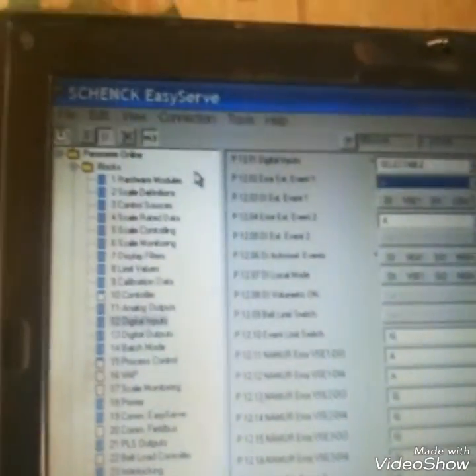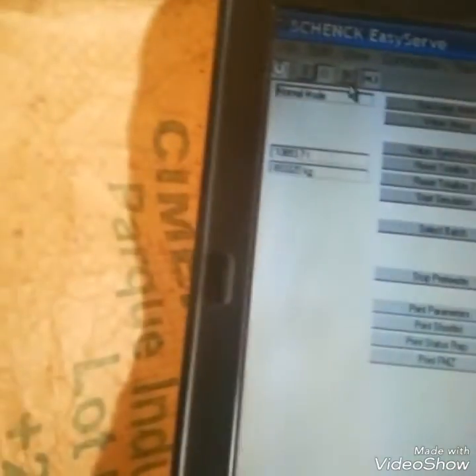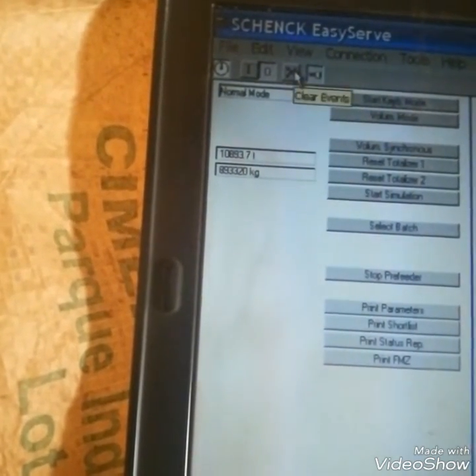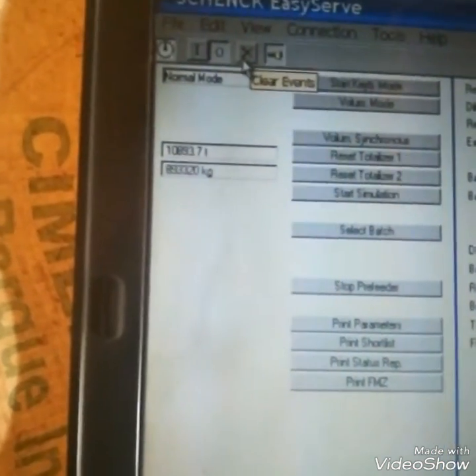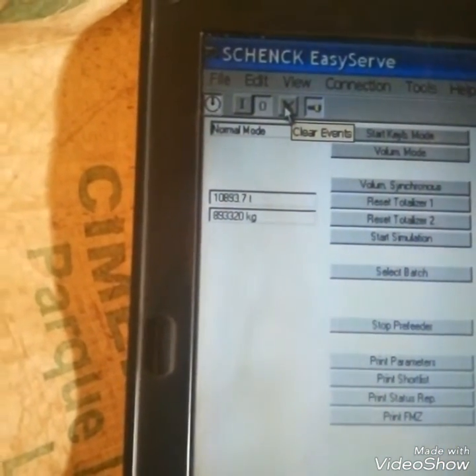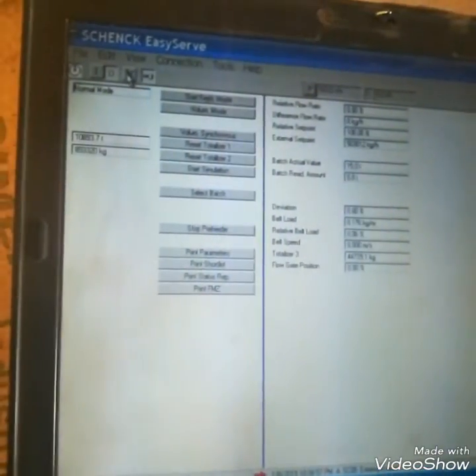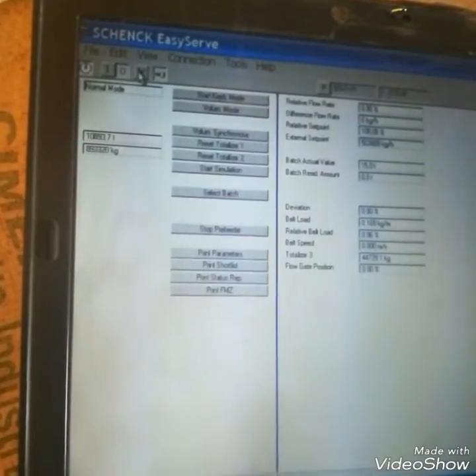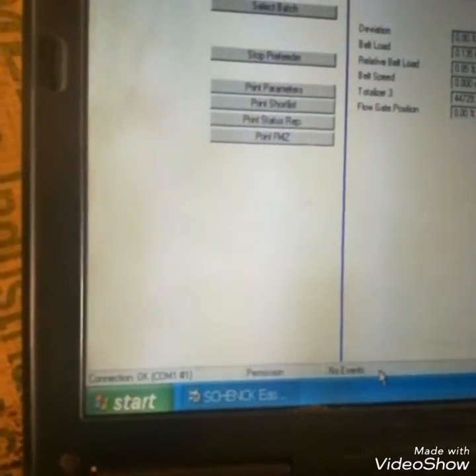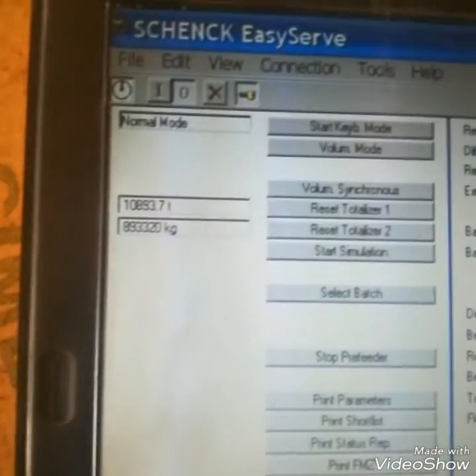So you can see I can configure alarm, warning 1, warning 2, and ignore. Warning 1 will show and it will need a reset. Warning 2 will be generated and shown, but it doesn't need a reset. Ignore means no fault will be generated, there will be no warning on the display. Now I can clear this event from this cross button. When I press this cross button, the fault will be reset. The event will be cleared. I pressed it and now it's showing no event. That means the event is acknowledged, the fault is acknowledged, and now it's ready to start.